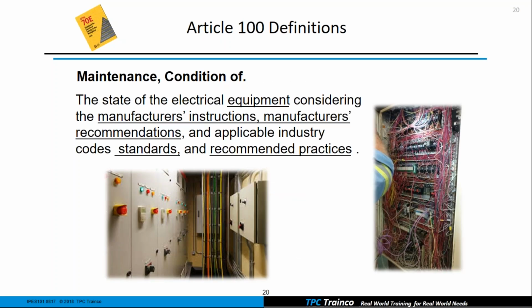Condition of maintenance. This one is a pet peeve of mine because sometimes it's real tough to satisfy this requirement out in the real world. And you can see that they've played with this definition a little bit because we have some words that are underlined. So the state of the electrical equipment, considering the manufacturer's instructions, which are real good. I mean, if we're going to maintain a piece of equipment, the manufacturer's instructions should help us tremendously. And manufacturer's recommendations. Then it goes on to say applicable industry codes and standards.